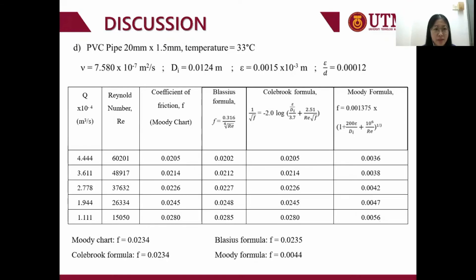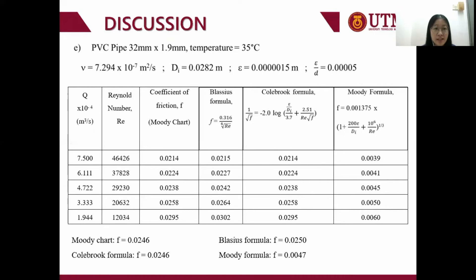Next is the PVC pipe with dimensions 20 mm × 1.5 mm. The coefficient of friction from the Moody chart is 0.0234. The Colebrook formula gives the same value of 0.0234. The Blasius formula gives 0.0235, and the Moody formula gives 0.0044.